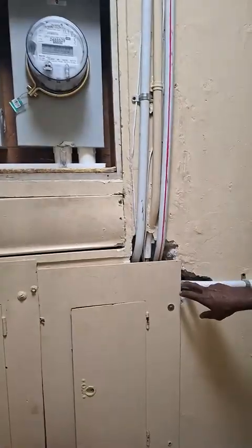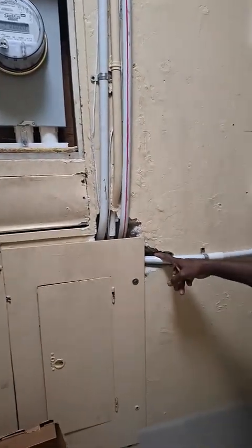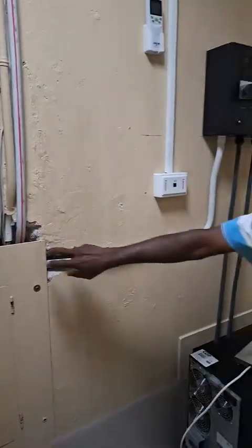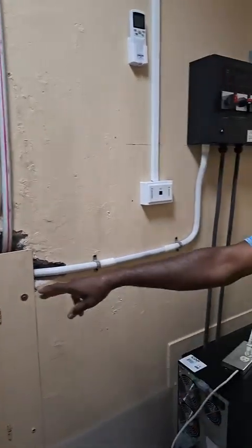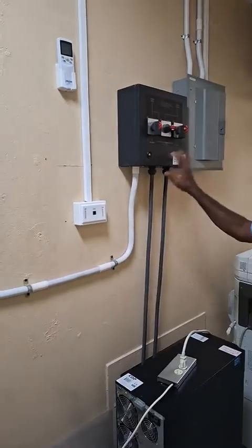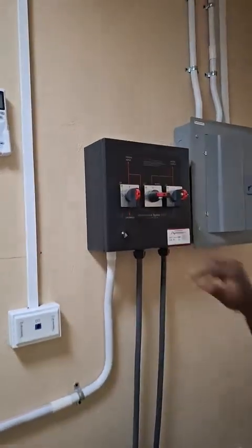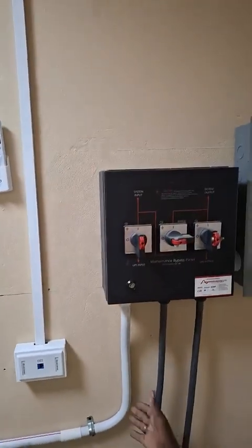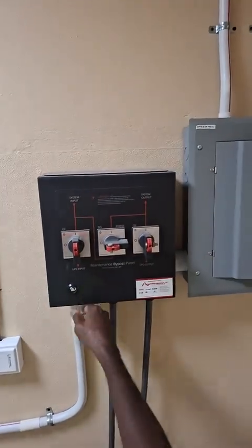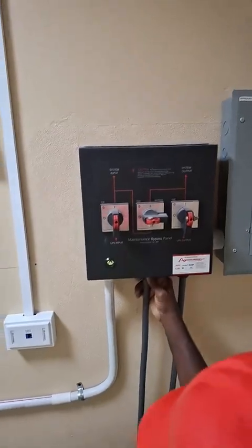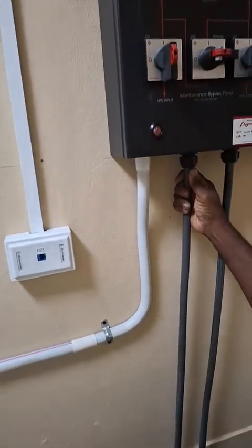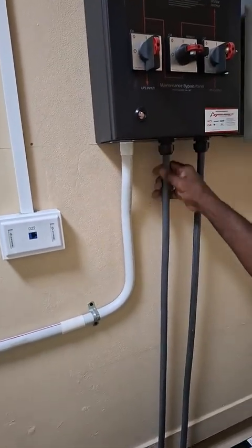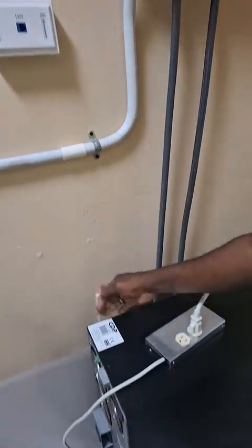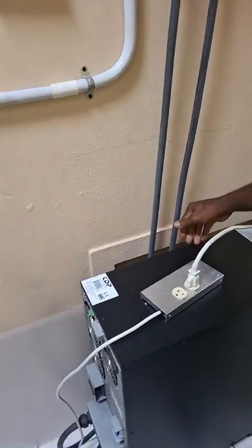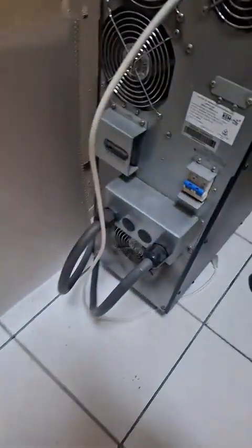We start from here, we get our utility supply, our JPS supply from here. We have this 3-phase panel, and we come to our transfer box, which is like a transfer switch. So what we have here is an input - the JPS input goes straight. Then we have an input from this combiner box that goes to the UPS, feeds the UPS, and then we have the return, the supply from the UPS, returning to the combiner box.